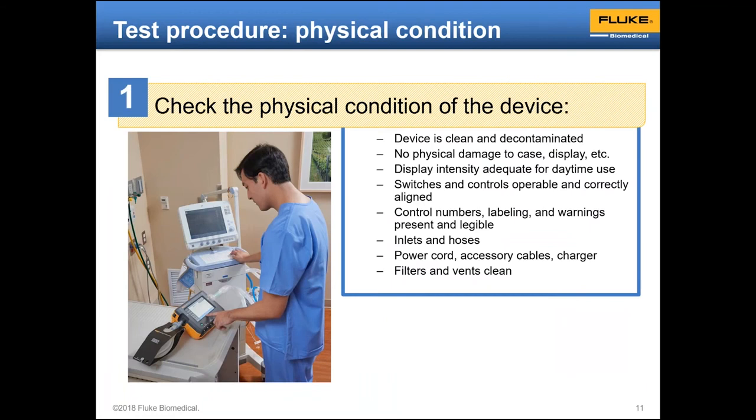All right, as I said yesterday, we will always evaluate the physical condition of the device. Is it clean and decontaminated to begin with? In this pandemic, it's very important that it's clean, decontaminated and disinfected before you even put your hands on it. As a matter of fact, these days, you probably ought to be thinking about wearing gloves as well as a mask and probably either eye protection or a face shield whenever you're working inside a hospital or medical facility.